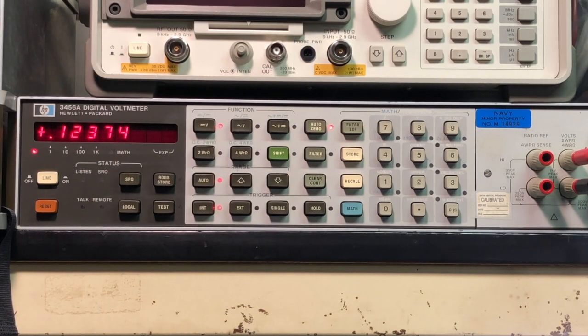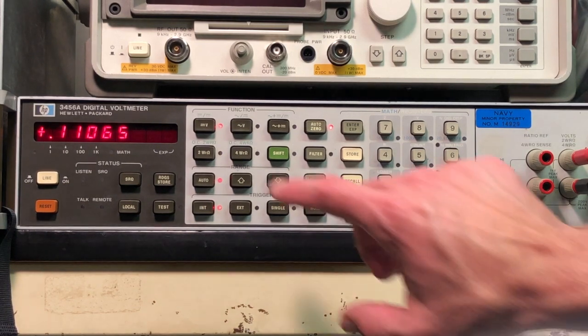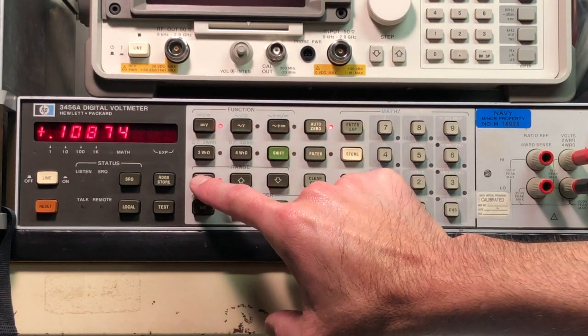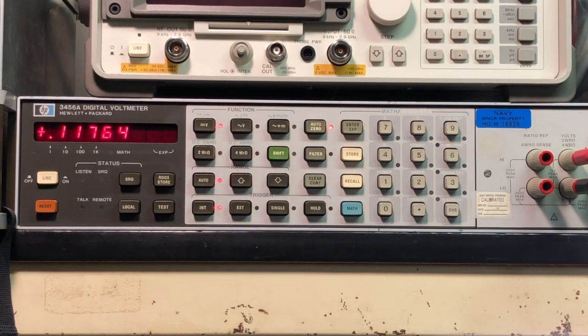All right, here we are looking at the Hewlett-Packard 3456A digital voltmeter. You can see it's set to DC volts and it's auto ranging. Now the numbers that you see fluctuating around on the screen are perfectly normal because the ground test probe is connected to a ground point on the circuit board in the frequency counter. It's a test point that they call out to use when you're measuring the voltages for the power supply.